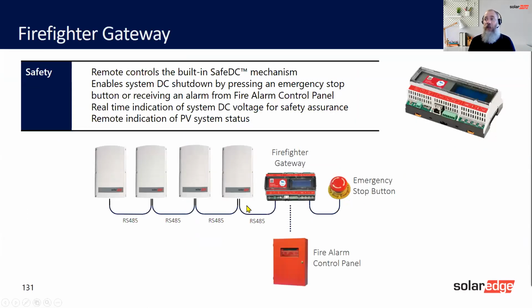A firefighter gateway. Firefighter gateway is a device. It doesn't do SafeDC. It doesn't control SafeDC, but it helps. These inverters themselves, as I said, if you were to turn the AC off, they would shut down to 1 volt per optimizer. If you were to disconnect the DC, cut the DC, if there was an arc fault and you had arc fault enabled, again, it would drop down to 1 volt. Even if you turn it off, it will drop down to 1 volt.